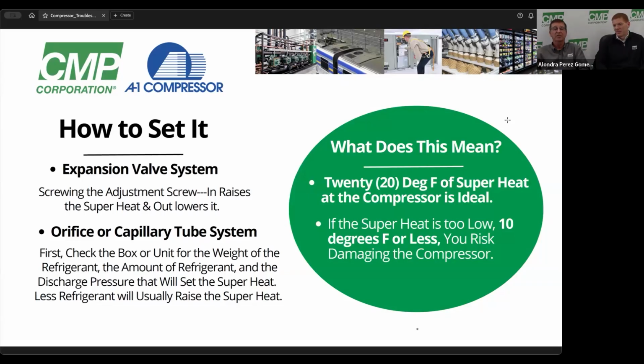It's going to do damage to the compressor, whether it be slow liquid coming in or a fast slug. Yeah, it's going to damage the compressor. And that's the big thing we need to, as a technician, you're out there. It's not only that evaporator superheat and setting up, you've got to set up the TXV to that evaporator. So if it's a 4 degrees superheat or 6 or 10 degrees superheat Fahrenheit or 5K, you need to set the evaporator superheat. But you have to check that compressor superheat or that system superheat like we're talking about here, because if you don't know if it's wet gas, liquid going back, and this just like we said, it can start wearing away on those parts.